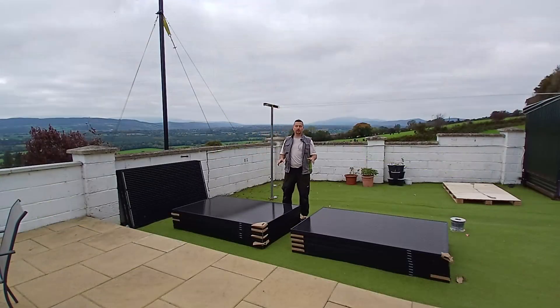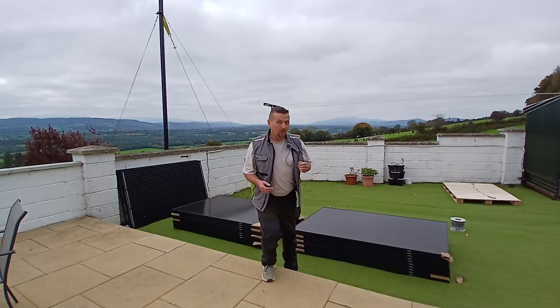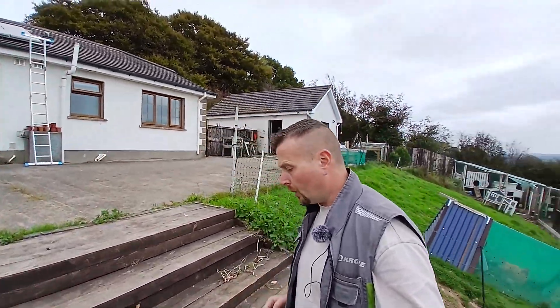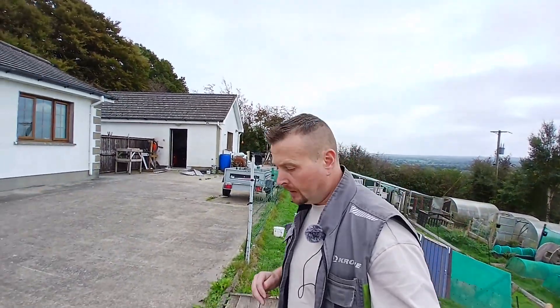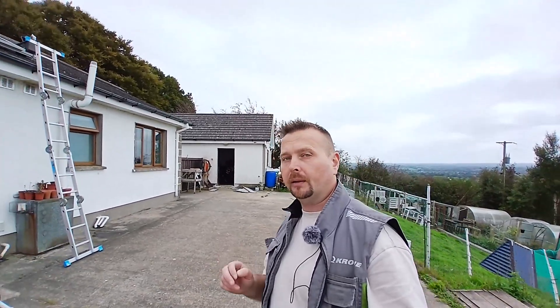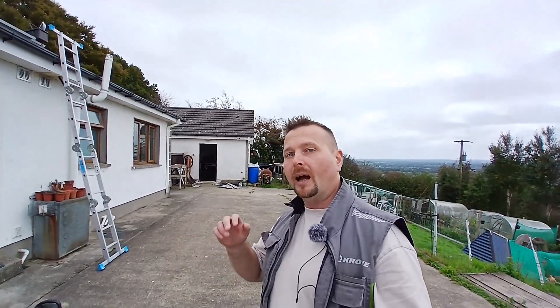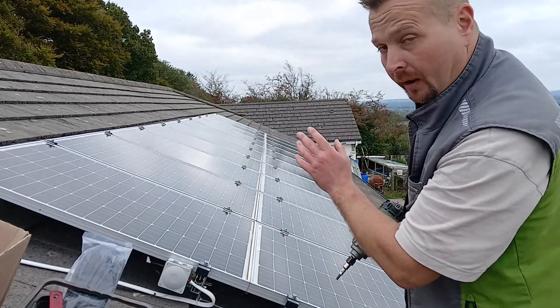What we've got here is 10.7 kilowatts worth of solar. After long discussion, Claude and I figured out how to incorporate this into our system and make it scalable for the future. All of our p-type panels will be replaced and we'll have four separate strings of panels. The problem is our current inverter only has two PV inputs, so for the moment we'll just lay the groundwork — all panels installed but operationally we can only use two of those strings. First thing is to disconnect and remove all the old panels.